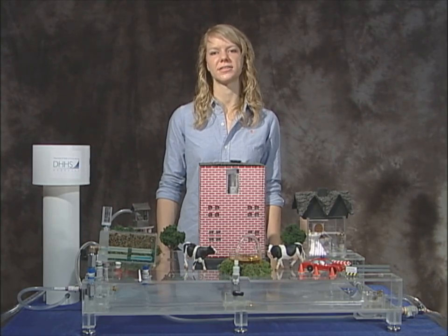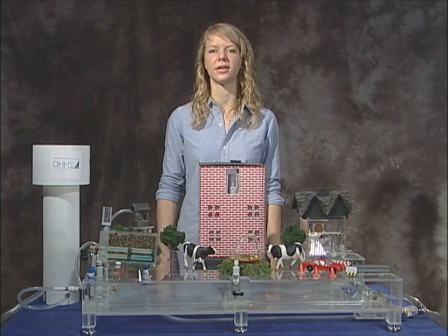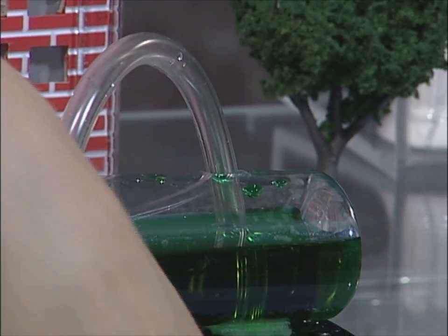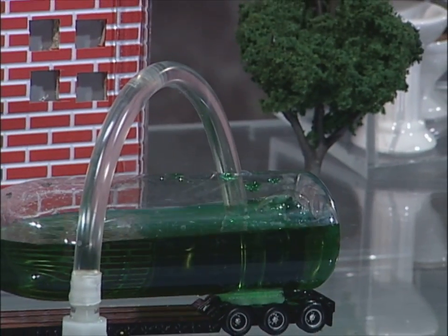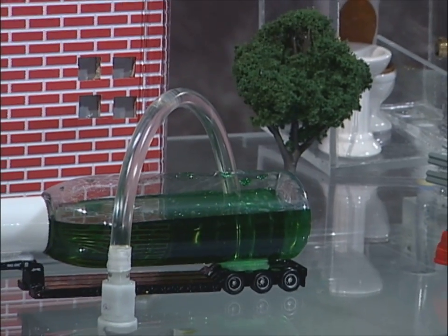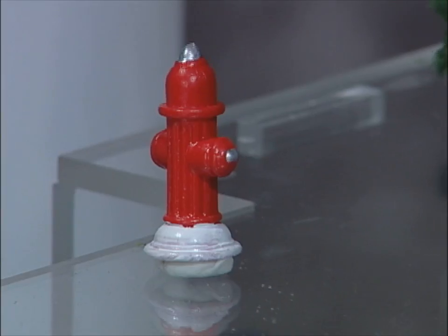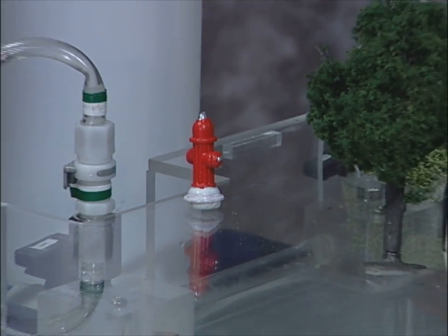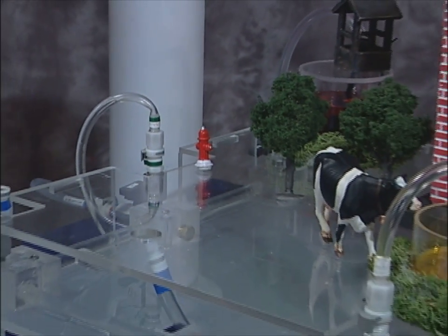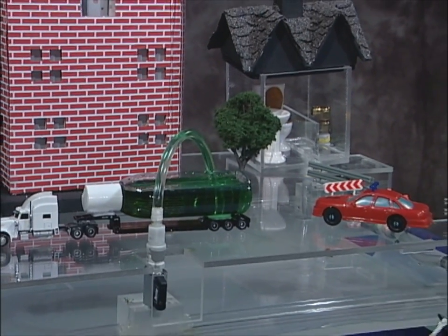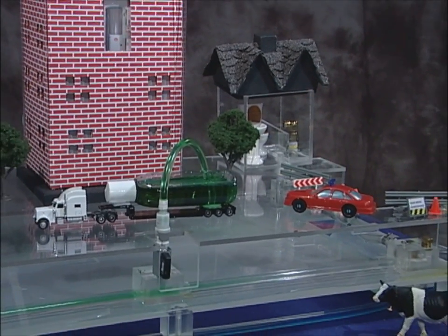Another alternative back siphon scenario is where an inlet line is filling a truck at a truck fill station without an air gap. In this scenario, the line to fill the truck is submerged in the contaminated water as the truck is being filled. Under normal pressure conditions, the flow is positive and fills the truck. If, however, a pressure loss occurs in the system, such as a fire flow scenario, the pressure drops in the public supply and contaminated water is siphoned back into the drinking water supply.